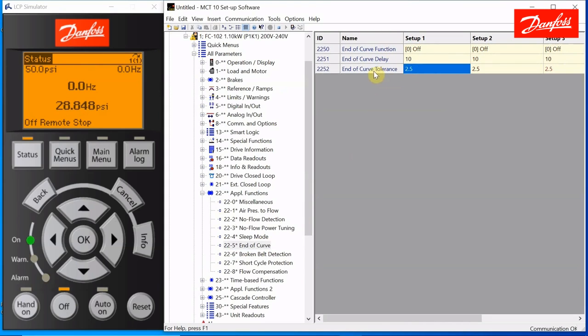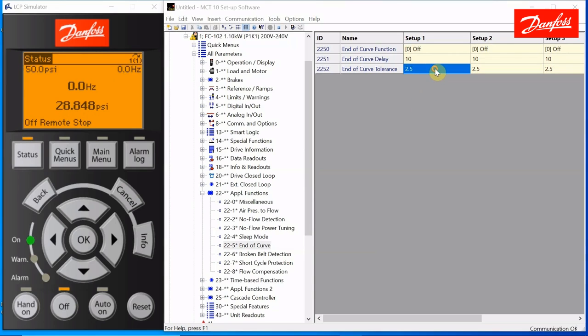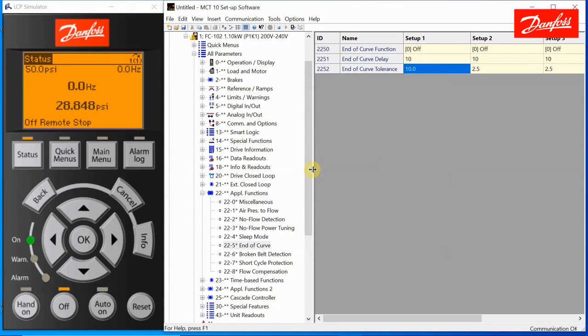Down here in the 22 group application functions, if you look down to the 22-5, there's the three end of curve parameters. Going from the bottom up, end of curve tolerance. That's a percent. It's a percent of full feedback, in this case 100 psi. So 2.5% of 100 would be 2.5 psi, meaning that if the drive is running at full speed and it cannot get the pressure to within 2.5 psi of set point, it declares that to be an end of curve situation. I'm going to change that to 10. It might make a better illustration.